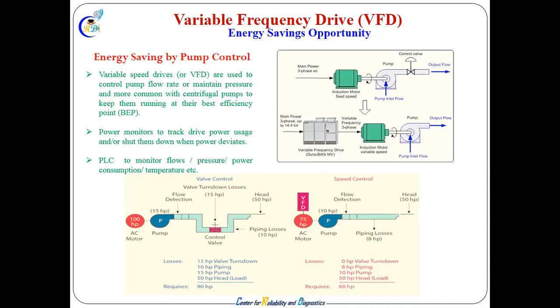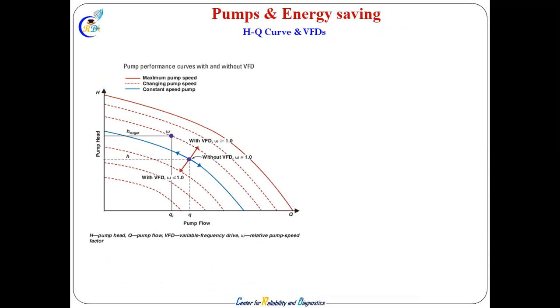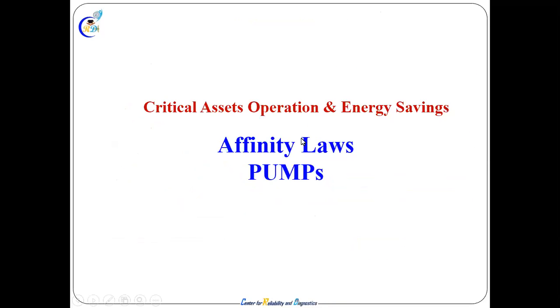while consuming 15 HP less. Calculate that in kilowatt hours, over the number of months and years, and it is a huge amount. And this is not the only pump; there may be many pumps like that. So, pumps and energy saving: now we understand that by using VFD, we can move this curve, the dotted line, up and down. Beyond the VFD, this is the best efficiency point. The blue one, and more up and down depending on the requirement. If you want a little more energy but need a higher flow requirement, you can always play with this. So that is what he describes here.